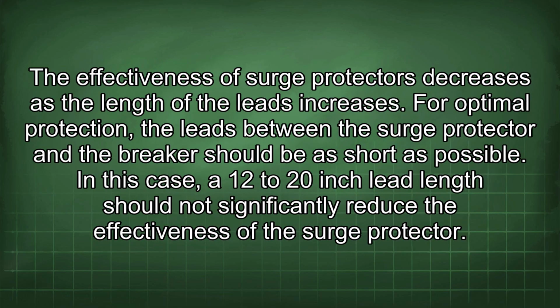The effectiveness of surge protectors decreases as the length of the leads increases. For optimal protection, the leads between the surge protector and the breaker should be as short as possible. In this case, a 12 to 20-inch lead length should not significantly reduce the effectiveness of the surge protector.